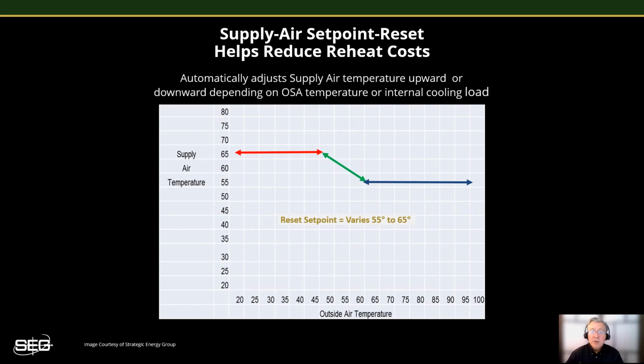This graph depicts a simple, automated supply air temperature reset strategy that's used by many systems these days. It resets the air handler's supply air temperature based on the current outside air temperature. It's a simple but very effective strategy that helps minimize the need for reheat out of the terminal boxes. It keeps the supply air temperature up around 65 degrees until the time that the building just begins to need cooling, usually as the outside air temperature rises to around 50 to 55 degrees. And then it steps the supply air temperature downwards slowly, providing cooler air as the outside air temperature increases, finally reaching its lowest set point of 55 degrees.